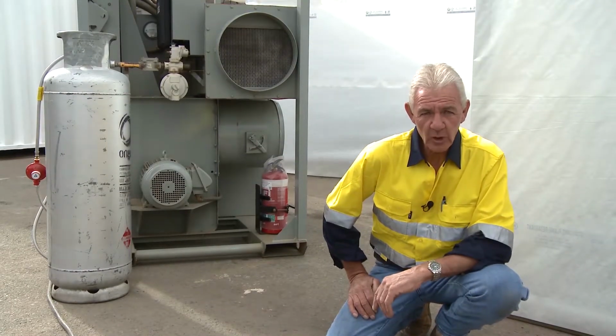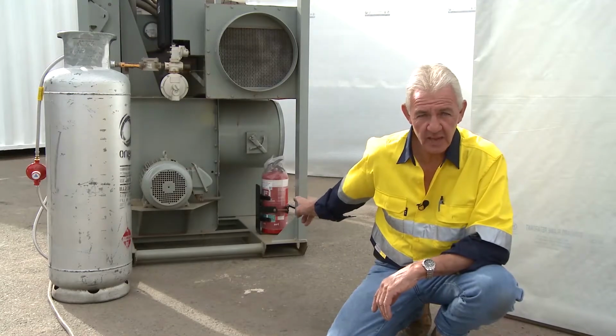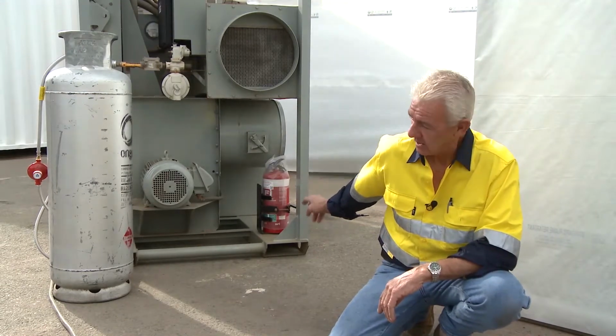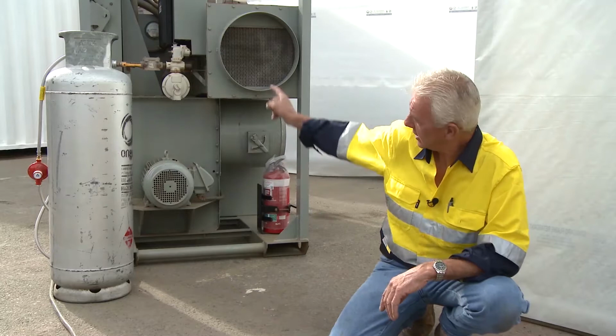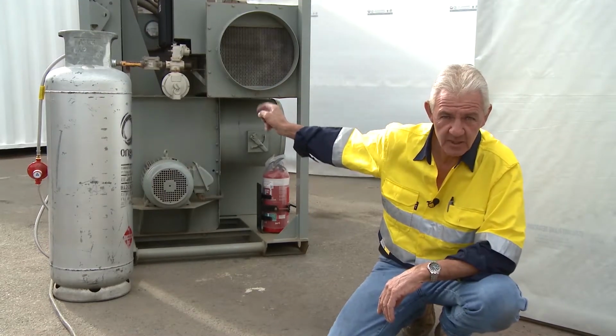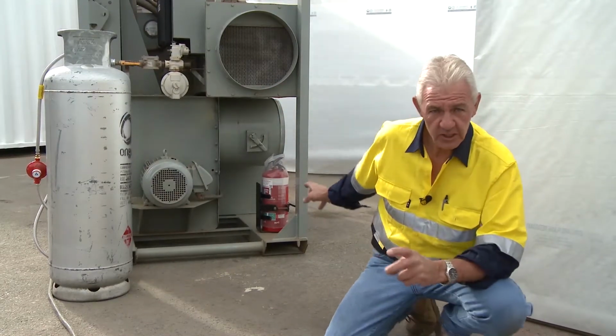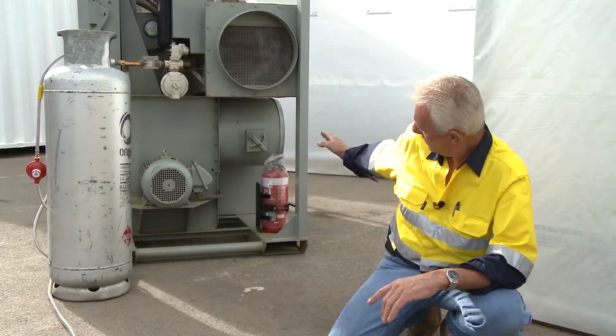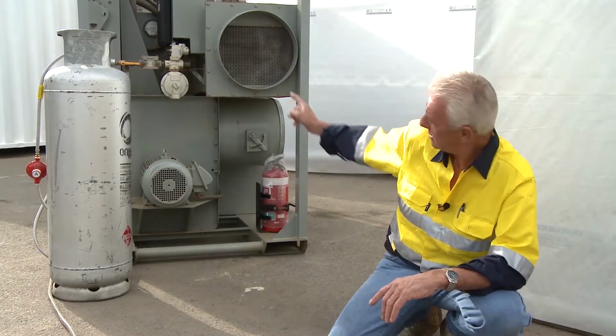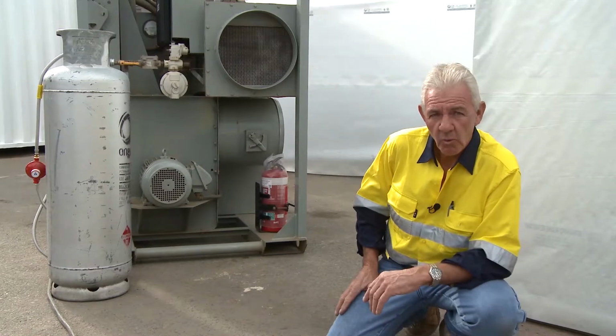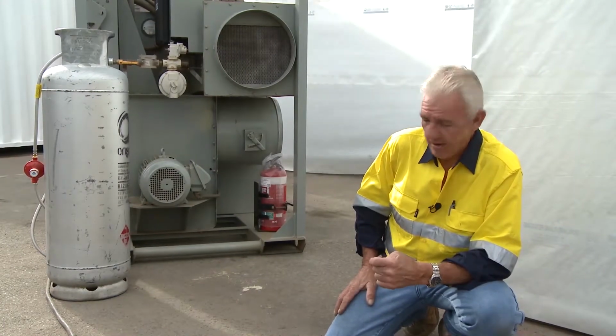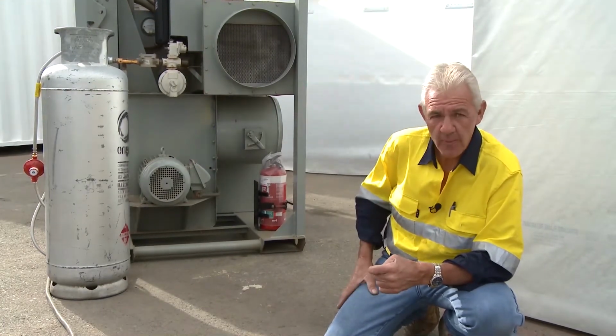So when we set this up earlier, you saw me adjusting that butterfly valve on the bottom there. That butterfly valve controls that magnehelic gauge. So what you've got to do is ensure that when you alter that butterfly valve, it is between 1 and 0.25. So the gauge is sitting in the appropriate place now.